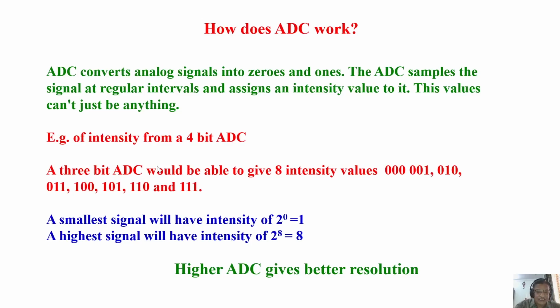And when it collects the signal, the smallest signal will be given the smallest value, and the highest signal will be given the highest value. Just to give you an idea, you take a sample with a huge, strong peak. For example, in a water-soluble sample, the residual water peak is very strong. A huge peak will be there. And if your sample peaks are very weak in intensity, they will be assigned low values, whereas the water peak will be assigned the highest intensity. That means that bit is full, so the highest intensity is assigned. This is how, when you sample, intensities are assigned for smaller and larger values.